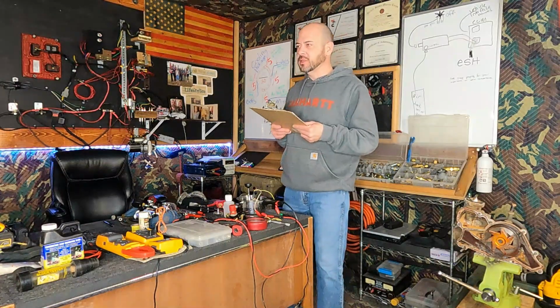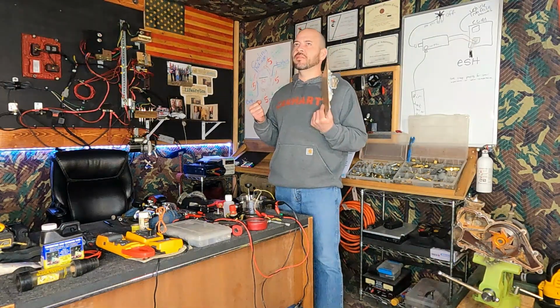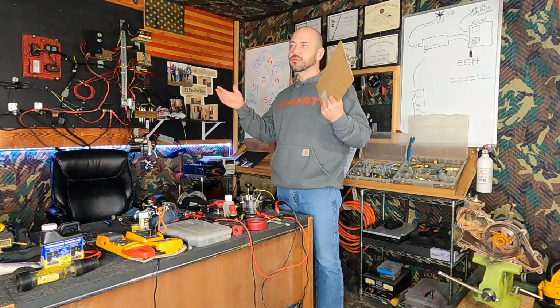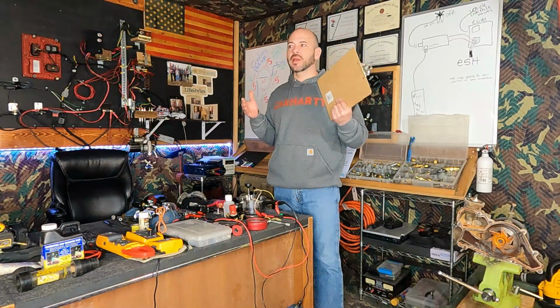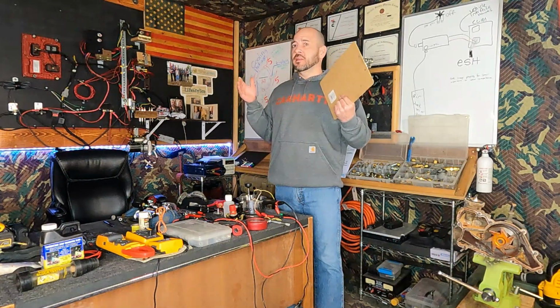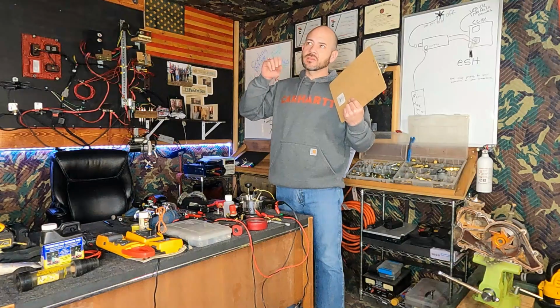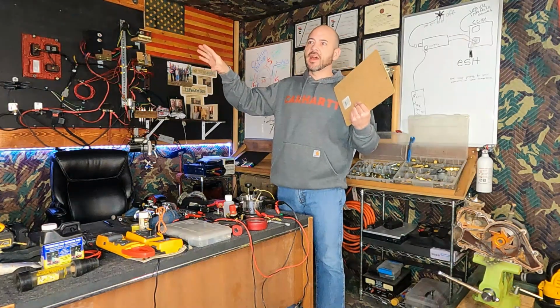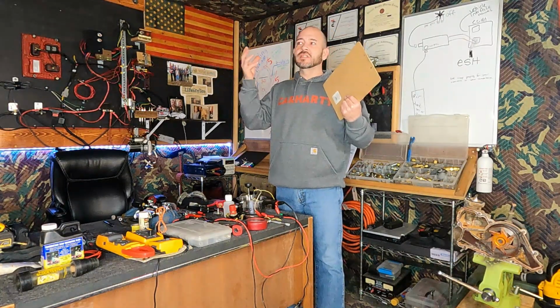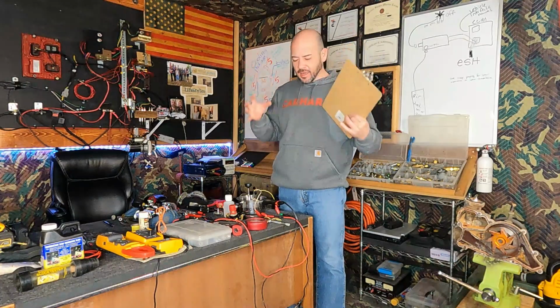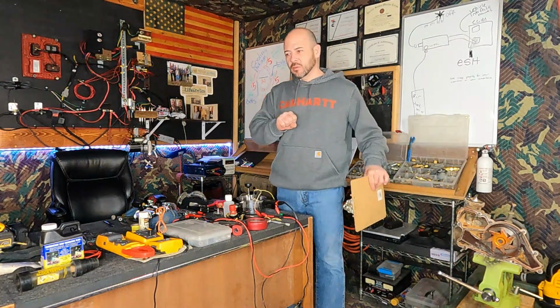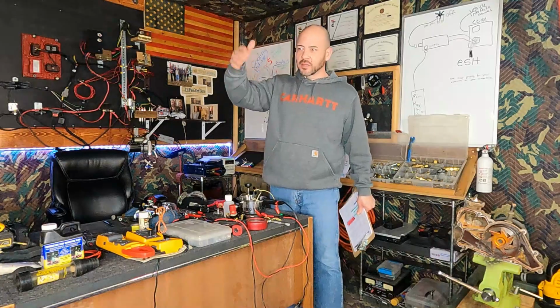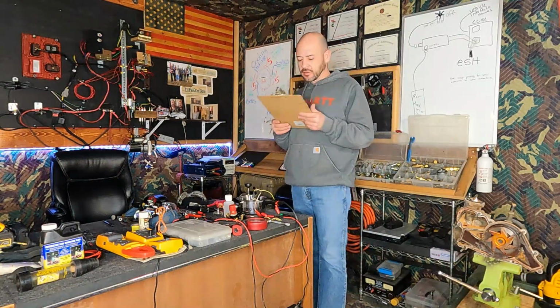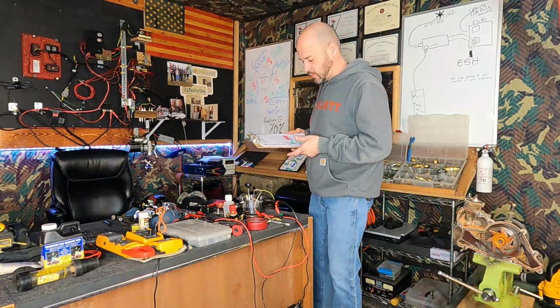The exhaust temps we're pulling these hills with go from 7, 9, 12 hundred degrees and up in that range, which is awful hot. All that exhaust temperature has to get out of the engine, and a lot of it doesn't, it's retained inside the iron of the engine, and needs to be removed through that cold air exchange over the cooling package. That's when we're getting into managing temperatures.